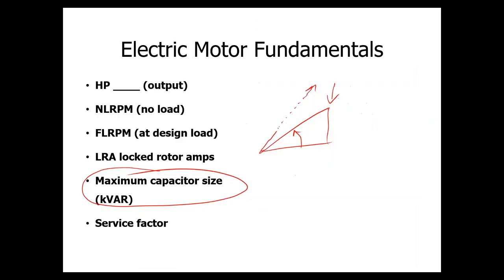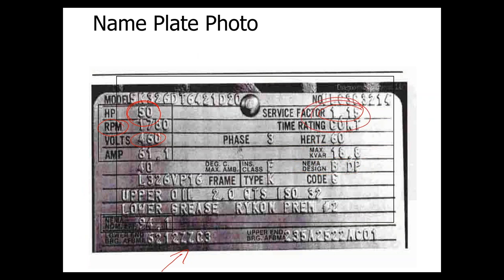Service factor is even easier. That's basically another way to say overload factor. That means you can run a motor overloaded a certain percentage. In this case, this motor has a service factor of 1.15, which means that it can be run 115% of rated load.